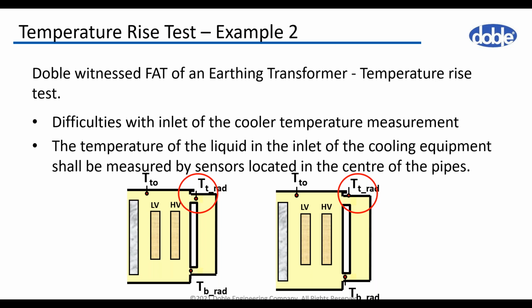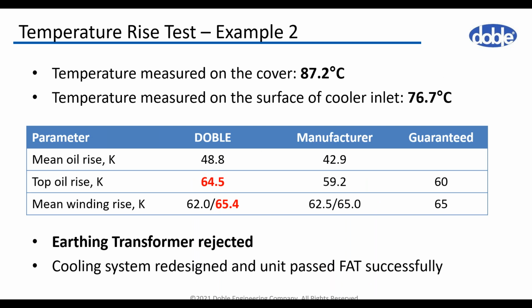But at that time, the customer didn't have the opportunity for any other measurements or to improve the test setup. And what we found during the measurement is that the temperature measured on the cover, in the special dedicated pocket, is much higher, or practically the temperature measured on the surface of the cooler inlet is much lower than the temperature on the cover.